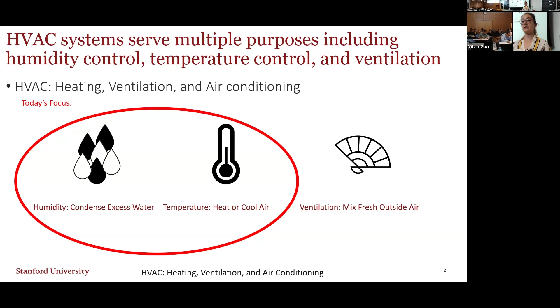HVAC are complex systems simultaneously trying to control humidity, control temperature, and provide sufficient ventilation. Basically, it's trying to keep humidity at about 50%, keep temperature at about 72 within the zones, and make sure you have enough fresh air so everyone stays healthy. Today I'll focus on humidity and temperature control, where I've found significant opportunity for savings across the contiguous US.